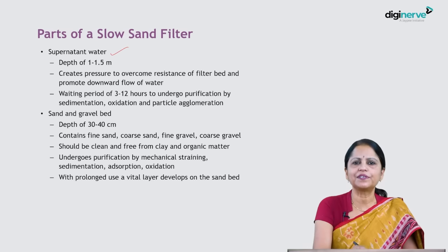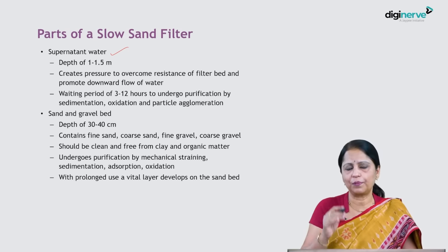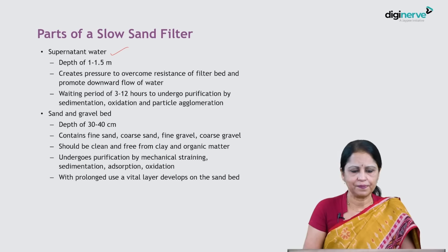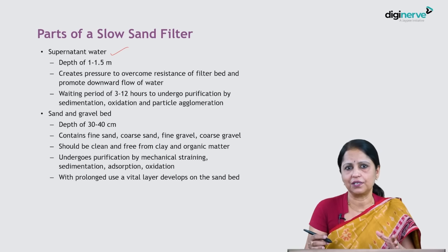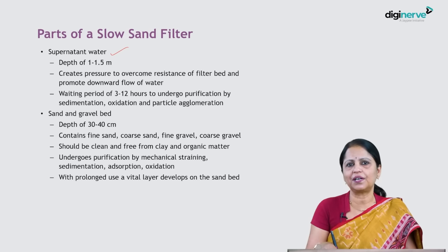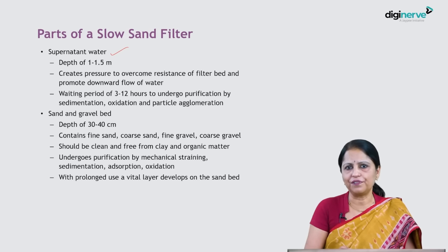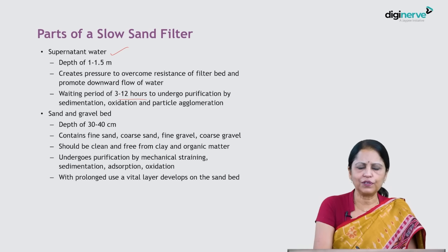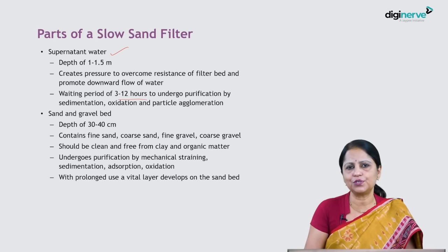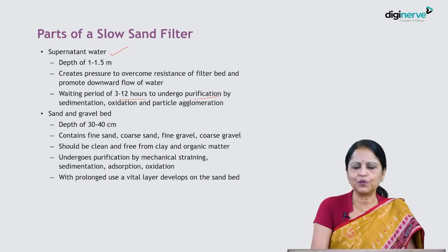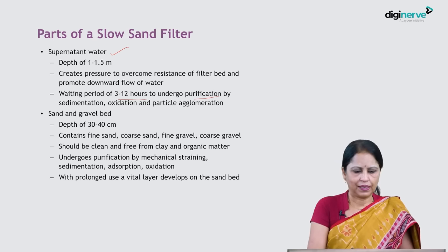On top there is the supernatant water. This is up to a depth of about 1 to 1.5 meter, and such a huge volume of water creates a pressure which helps the water to trickle down through the sand that is placed below the water, on the filter bed. And along with that, the volume of water that has a waiting period of 3 to 12 hours again undergoes purification by sedimentation, oxidation, etc.